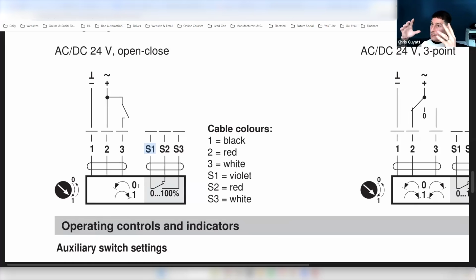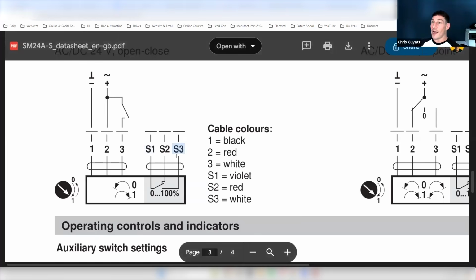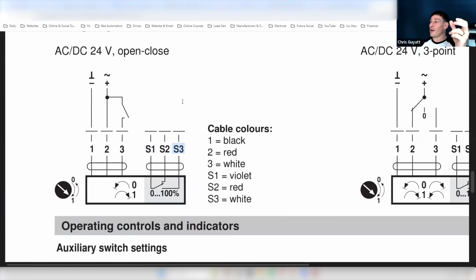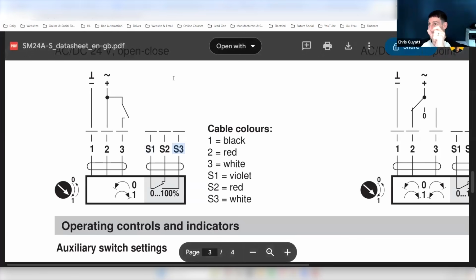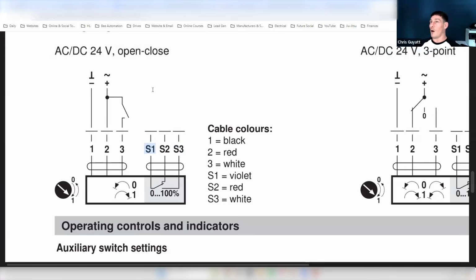So if we're thinking in terms of a BMS system, we could just think of it in simple terms, like we could have two lights on the front of the panel, one that says open, one that says closed. So S3 would go back to our green light, let's say, on the front of the panel that indicates this ventilation duct is fully open. And then S1 would be wired back to the red light that says that damper is fully closed. Not that we'd necessarily be doing that in a real BMS system, but that just gives you a taste of what we're doing there with these control signals. And then with that, Chris, you could take that back to a 2-pole relay, couldn't you, to get both your panel lights activated and also back to your PLC.